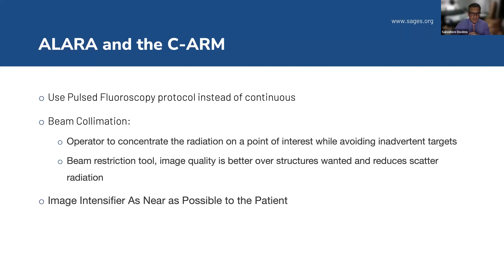The collimation, as I mentioned before, allows the operator to focus the radiation on a point of interest. Basically, if you can imagine, there are essentially lead panels or plates that come into the center. When you fire the X-ray, it's going to be viewed only upon that very specific structure. So it restricts the amount of radiation to only the objects that you want to focus on. If you only want to focus on the biliary tree, you can simply close the collimation beams and focus only on the biliary tree. And then, as I mentioned earlier, keep the image intensifier as near as possible to the patient. It's going to get you really clear pictures, and it's going to limit the amount of radiation scatter.